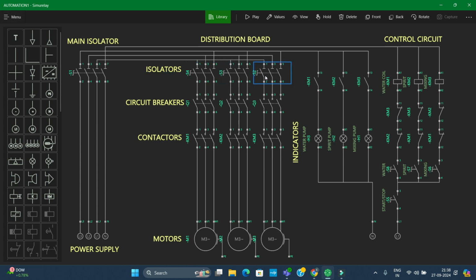So that means your control panel is going to have three isolators and three circuit breakers. An isolator is only a switching device - it's not providing any protection. But a circuit breaker is going to be a switch as well as a protection device. So in case there's an overcurrent somewhere or a short circuit, this circuit breaker is going to open up, unlike an isolator - once you've switched an isolator on, it is purely mechanical.